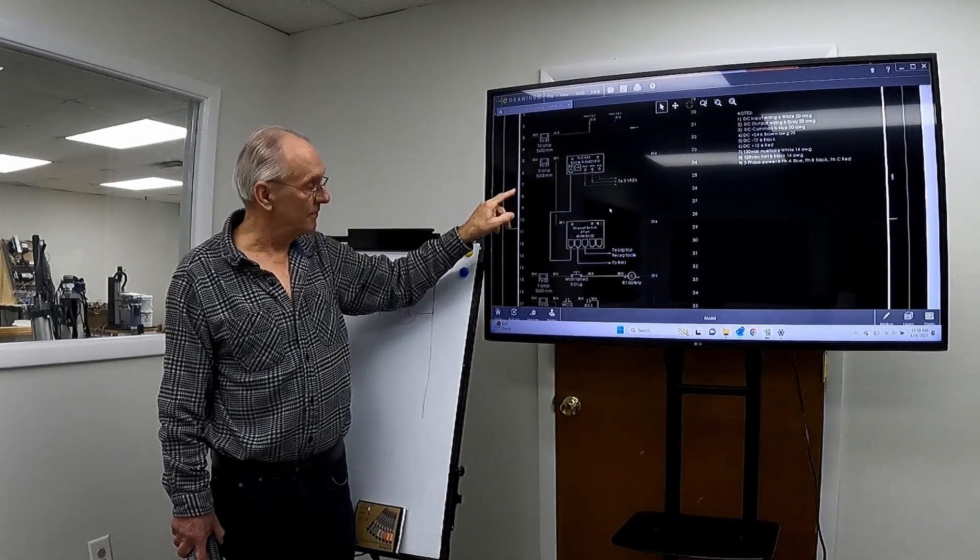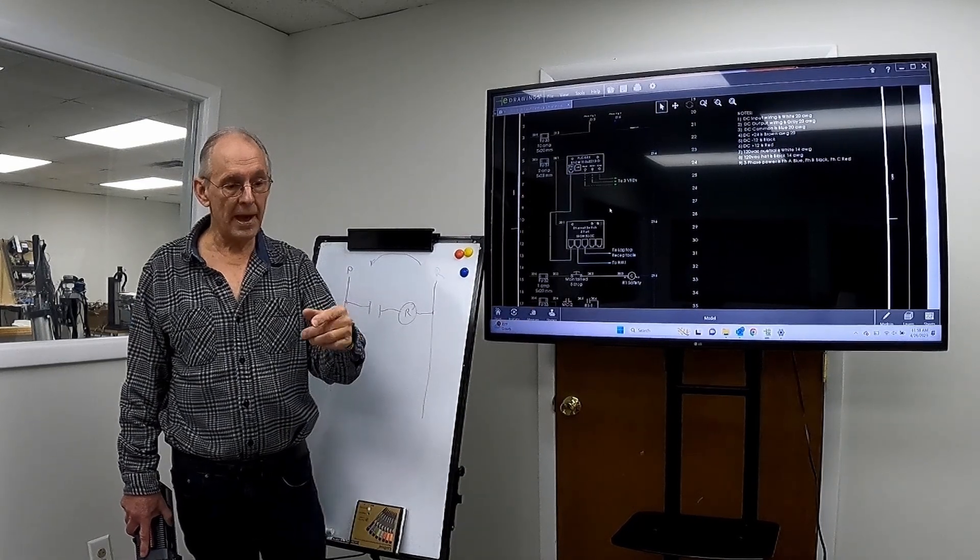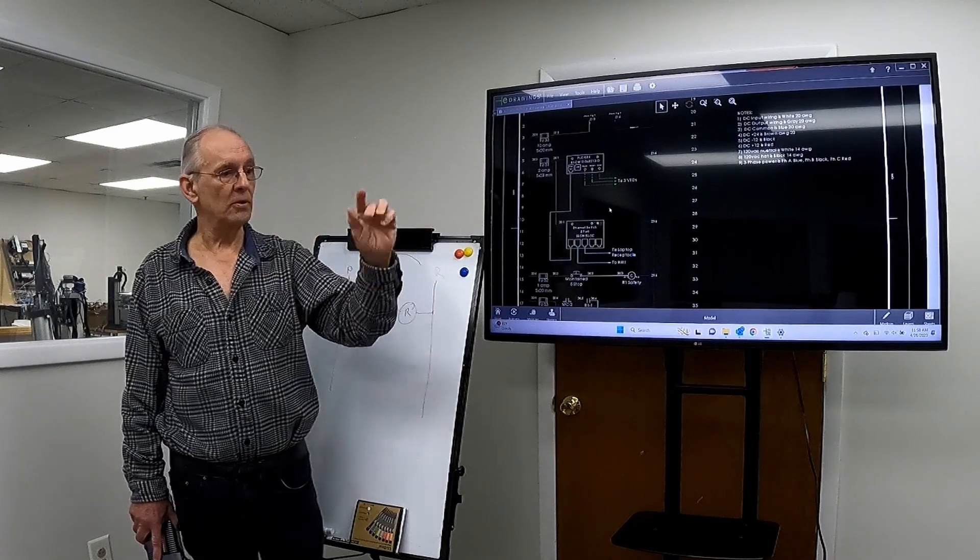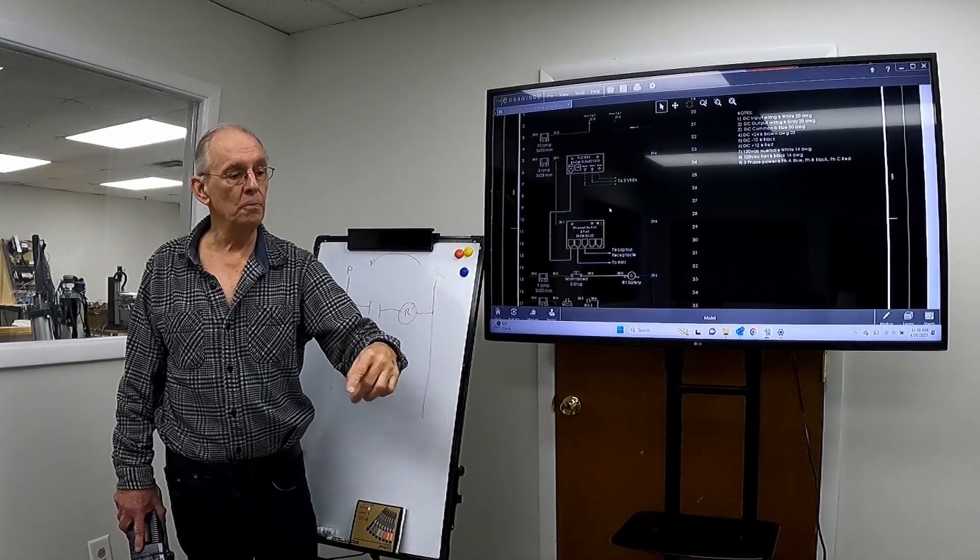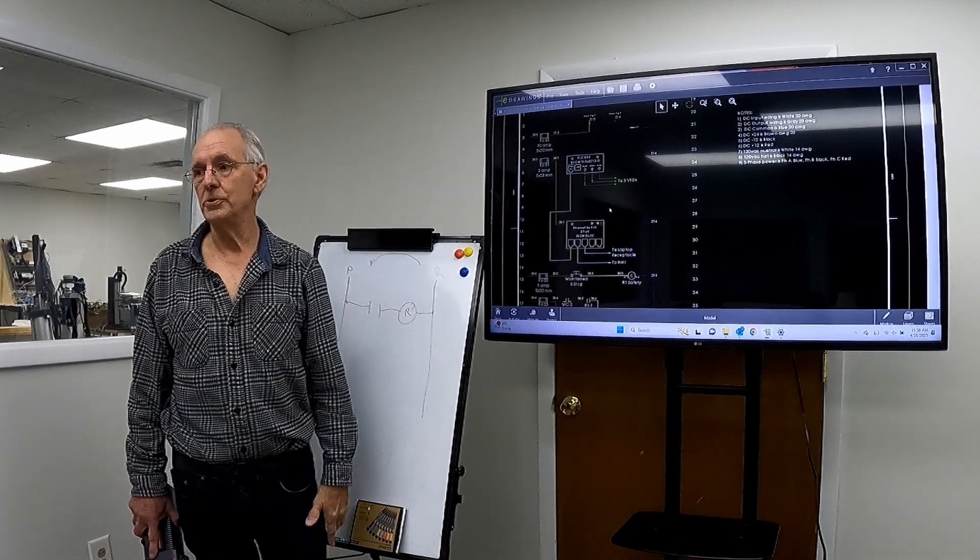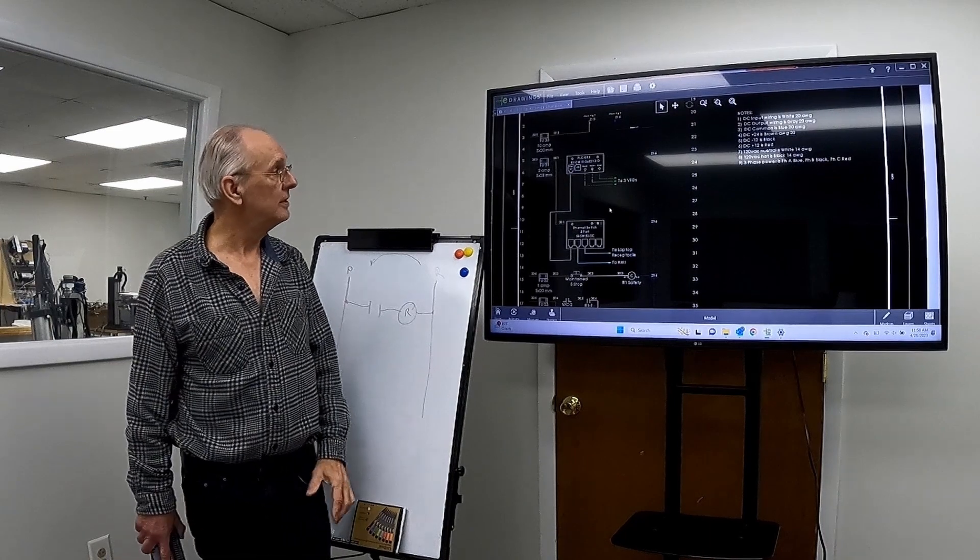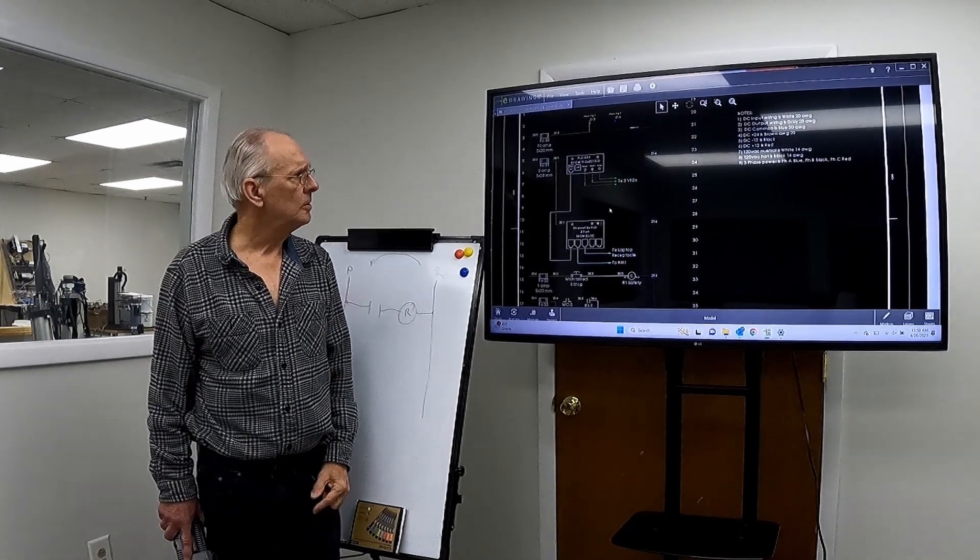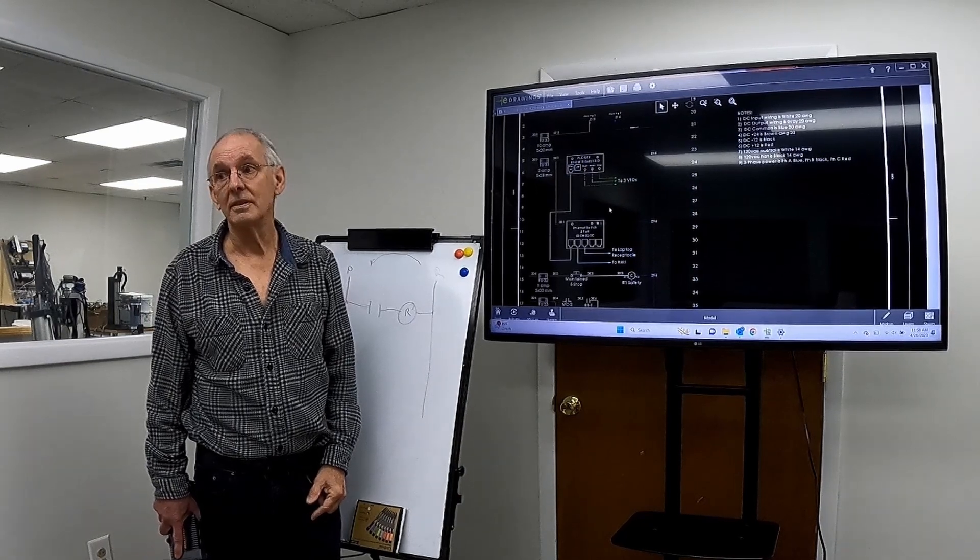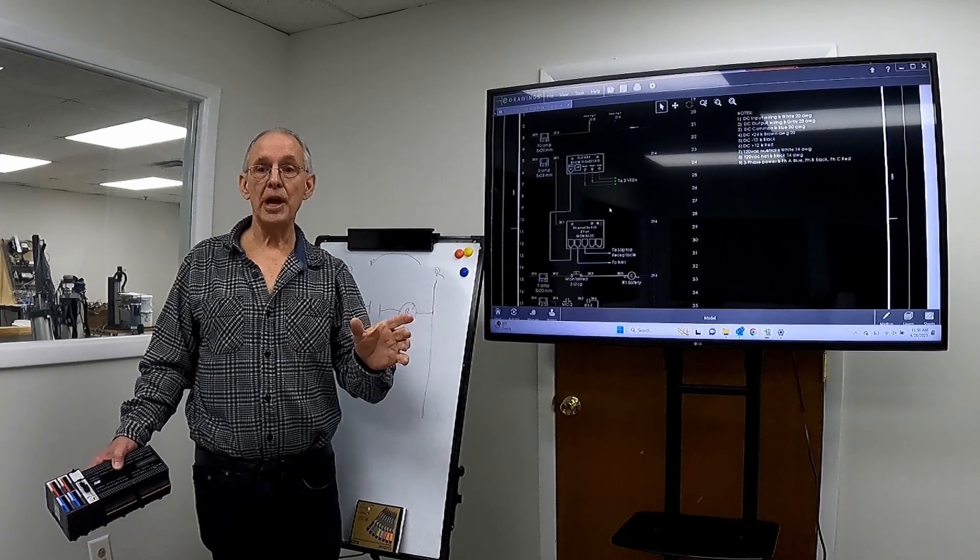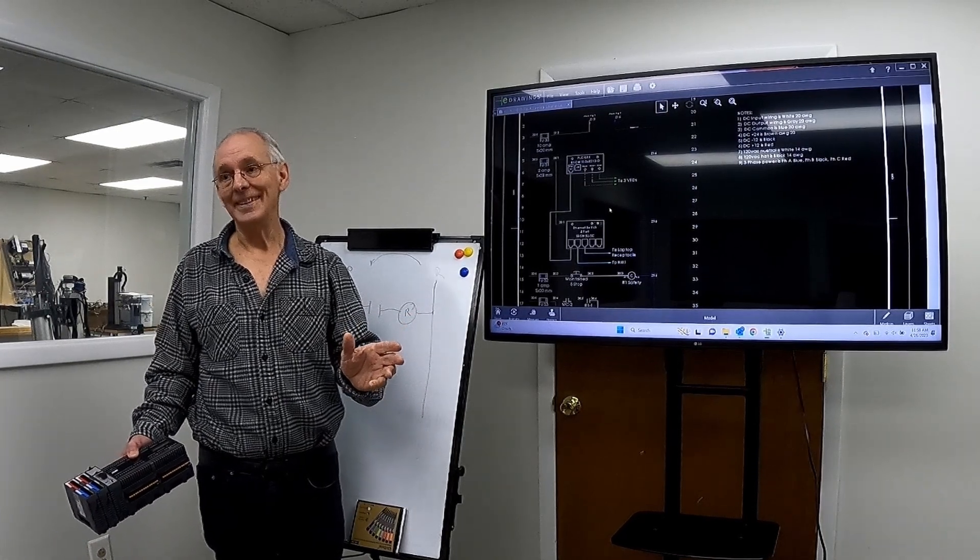So that's how, right? So you'll see in our panel, where we have the first fuse in a row of fuses, and the wire comes off that first fuse, off the bottom of it, loops underneath, and comes back to the top to a whole row of fuses. Okay, so I just want to - so even though it's drawn like it's coming in from the same side, physically in the box, you're saying the bottom will come out and go to the top of the next fuse? Yes. Okay. Yes. Again, schematic shows you how it works, doesn't show you how it's wired. I see. And that's why I'm saying there's a difference between a wiring diagram and a schematic. In the wiring diagram, they would show you that the wire was routed from one fuse and then to the top of the other fuses, but that's not how - that's not what a schematic does. Schematics explanation is how it works, and that's what we're seeing here.